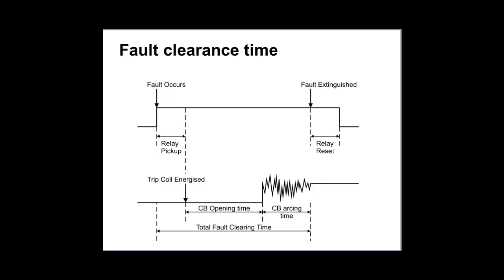So what will happen then? Well, a trip signal will be sent to someone else. And who is that someone else? The circuit breaker. Okay, so can I say that as soon as the circuit breaker receives the trip signal from the relay, it will operate? No. So what will happen inside the circuit breaker? Well, that circuit breaker has got a trip coil. When that current is received from the relay, that trip coil will be energized. So can I say that the circuit breaker will operate as soon as the trip coil is energized?